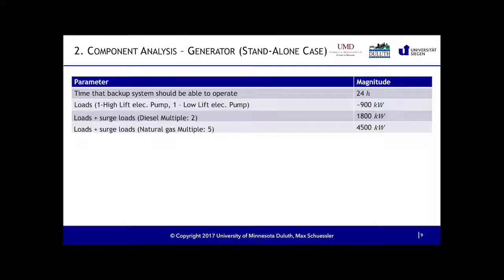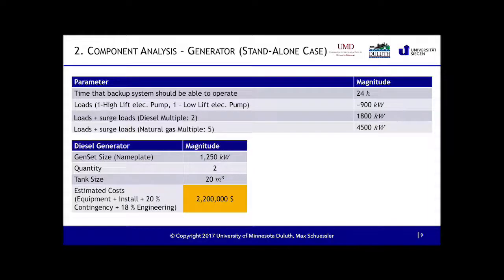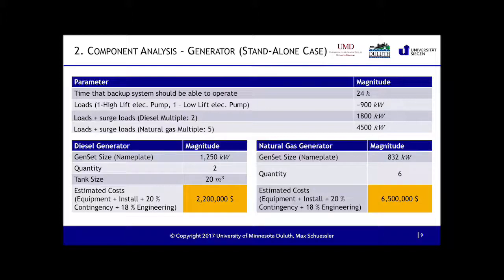This is how I came up with, or rather a preliminary study done by MSA from the Twin Cities, that we need 1.8 megawatt of power for a diesel generator or 4.5 megawatt for a natural gas generator. What this boils down to is that our total cost for the diesel generator sums up to 2.2 million, and for the natural gas generator, or genset, we have $6.5 million, which means the diesel generator option for such a huge load as the Lakewood plant is just the most feasible solution. This might change if we are looking at much smaller loads. Then natural gas might be an interesting solution, because on smaller scales, natural gas is usually cheaper than diesel generators.